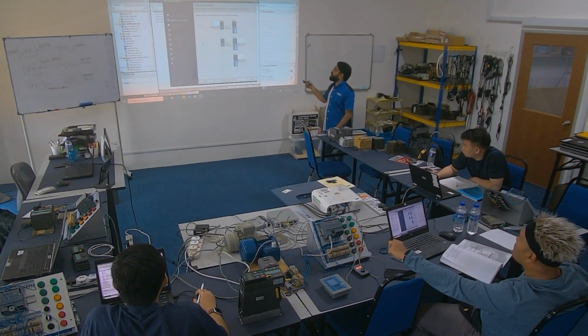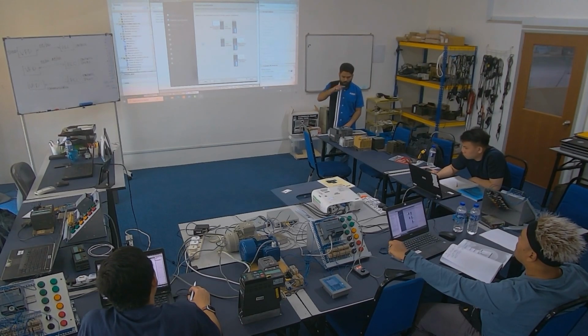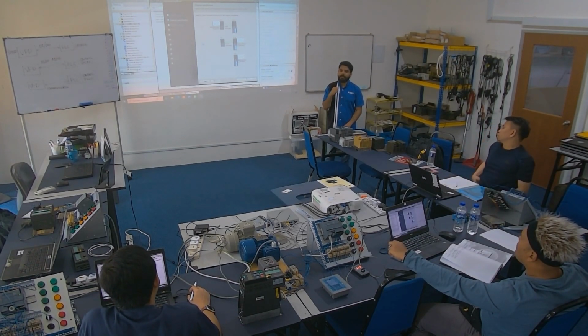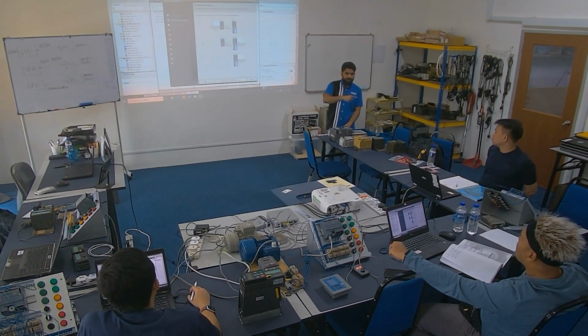Now this one also, if I choose this one, the PLC function is just to send the motor speed and just push, that's all. So inside the drive you have the ramp up, so the motor slowly, let's say you put 50 Hertz, then the ramp up time you put 2 seconds, so from 0 to 50 Hertz it will take 2 seconds to reach 50 Hertz. Then when you press stop, from 50 to 0 it takes 2 seconds, for example. So that 2 second setting you have to do in your drive.